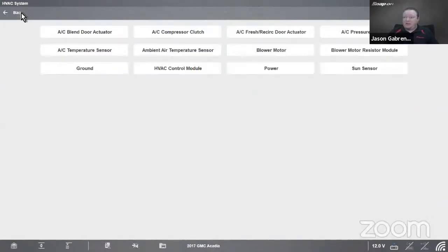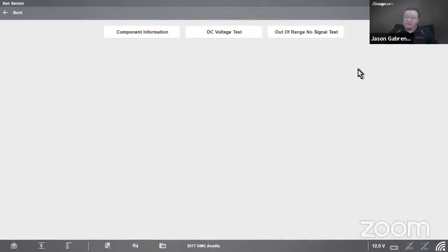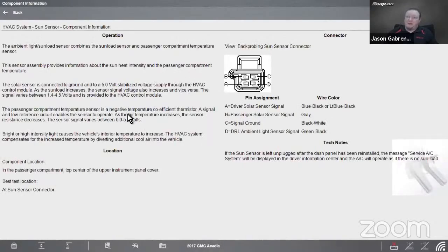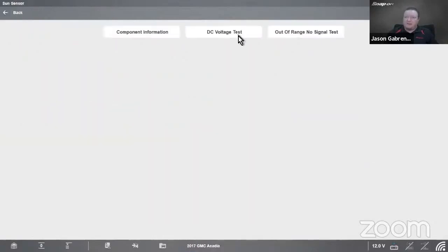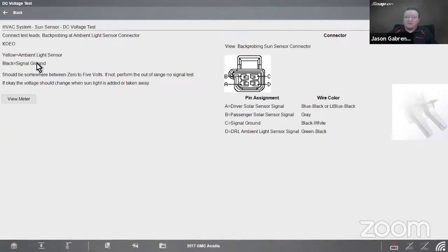All right, so that's testing a couple of things. The sun sensor's in there too, so we can do a voltage test on the sun sensor. That's a 0 to 5 volts output signal is what we get. To test it, it should be somewhere between 0 to 5 volts. If not, perform the out-of-range signal test. If it's okay, voltage should change when sunlight is added or taken away. So you can do this out in the sun, put your hand over it, and you should see the voltage go up and down as we do that.